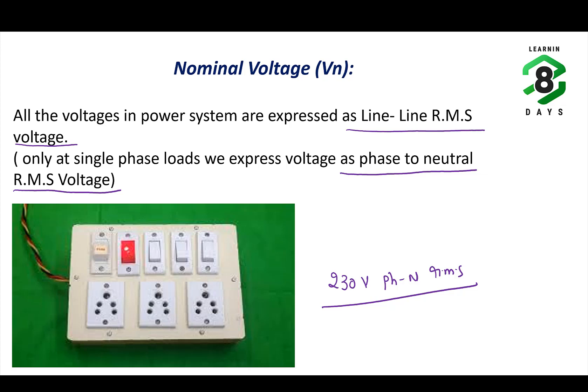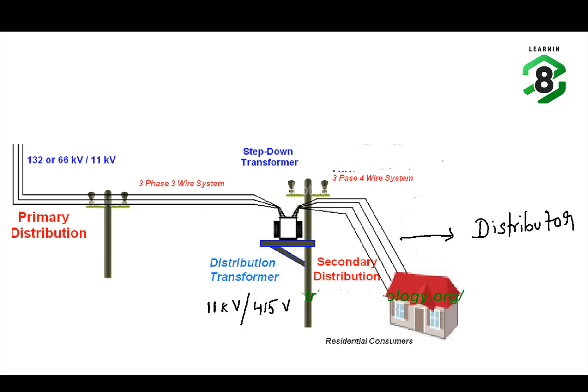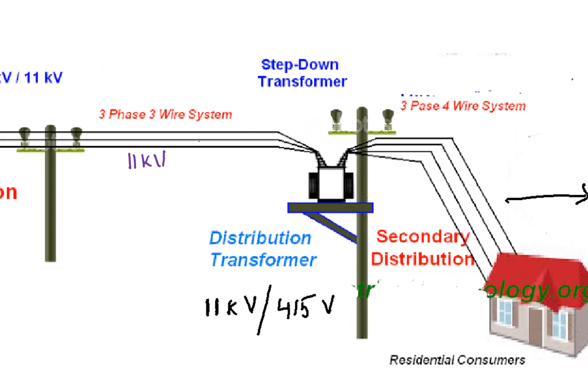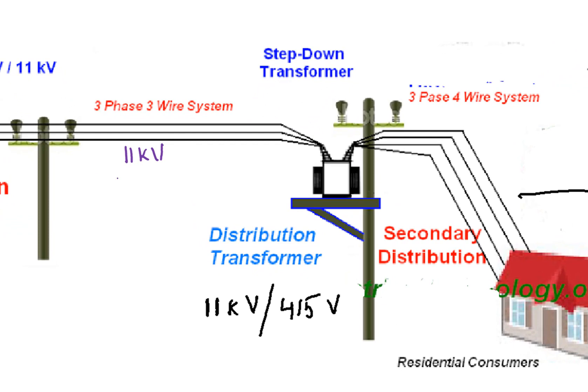However, if you take a multimeter and measure the actual voltage, it will never be exactly equal to 230 volts — there will always be a deviation. If you measure the voltage between phase and neutral of your three-pin plug point a hundred times in a day, not even once will you achieve exactly 230 volts. The actual voltage will be plus or minus this 230 volts. So we call 230 volts the nominal voltage. Looking at a portion of the system diagram, if a distributor's nominal voltage is 11 kV, that means the line-to-line voltage between two phases of that distributor is 11 kV.